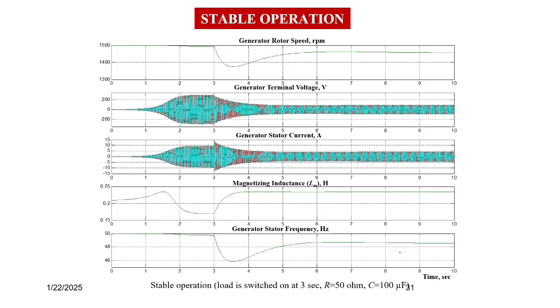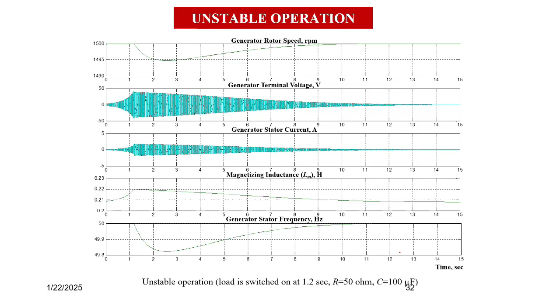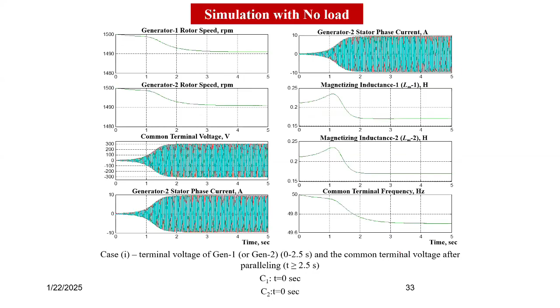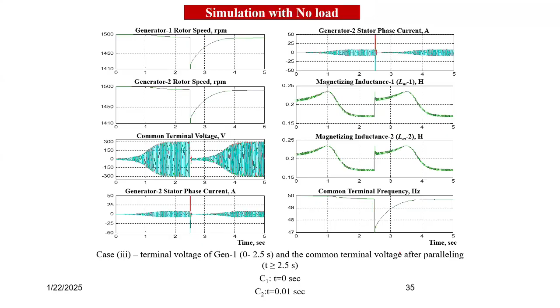Before completing the process, for example, instead of operating at 3 seconds, if the load is connected at 1.2 seconds itself, then what will happen is that the self-excitation will collapse. That is what we call an unstable operation. In fact, we tested parallel operations, everything. This is fundamental information with respect to the generator.